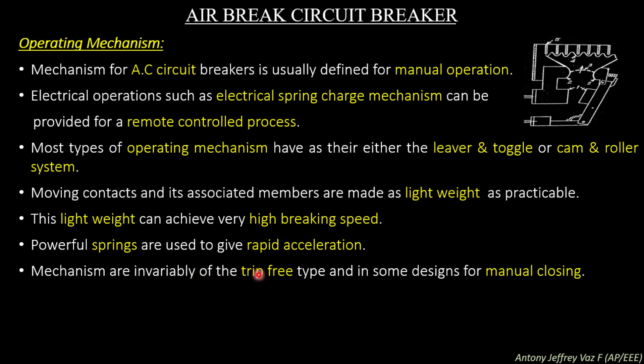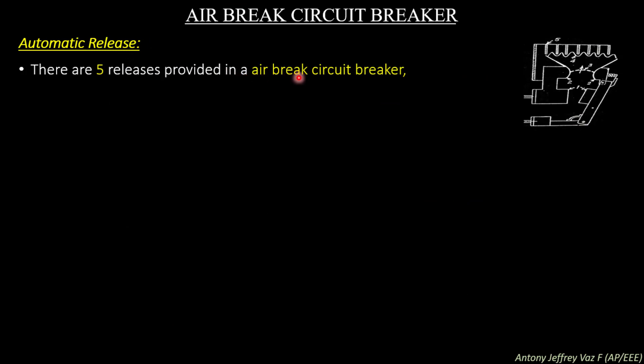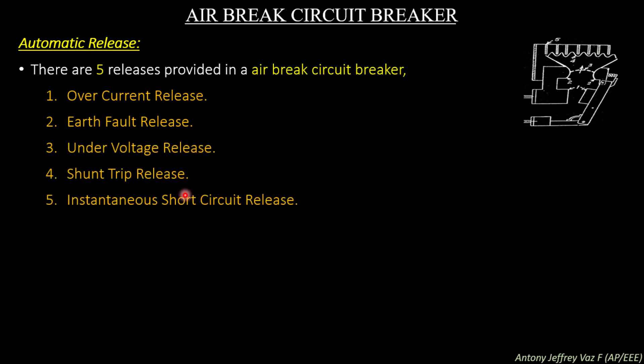Mechanisms are invariably of the trip-free type and in some designs for manual closing. Air break circuit breakers are made for automatic opening but the closing procedure is manual. A device makes immediate tripping if any reversal occurs in the direction of motion of the operating handle. Automatic tripping can also be achieved using electromagnetic spring automatic release. There are five releases provided in air break circuit breakers: over-current release, earth fault release, under voltage release, shunt trip release, and instantaneous short circuit release.